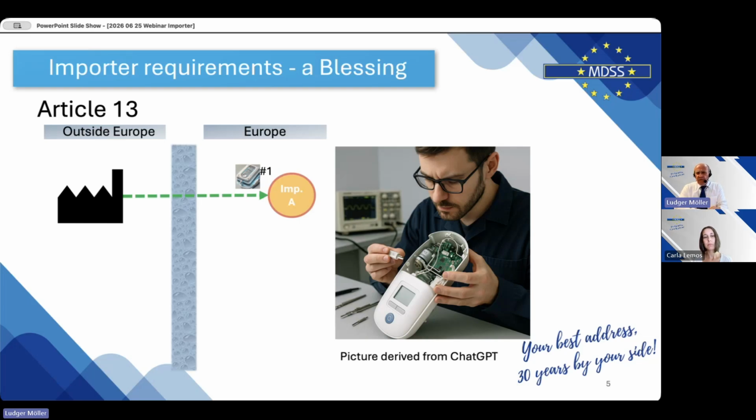It is because if the requirements would not be there, then the importer would have to check very closely the products he is buying, because he is the one who's making the product available for the very first time. And if he is selling it to somebody else, a distributor or patient, hospital, etc., he will be the one who is going to be liable, because he should identify obvious things. And if you look at the regulation, there are obvious things to check and not more. And that's what the requirements are for an importer. And if those requirements are not there, then the check could be going much deeper, opening up the product.